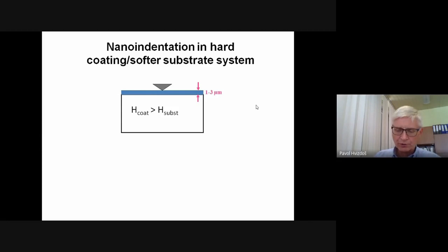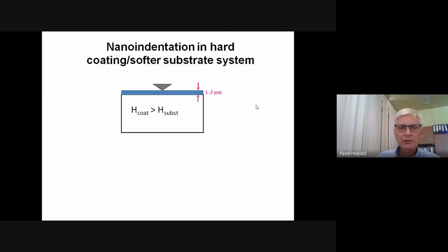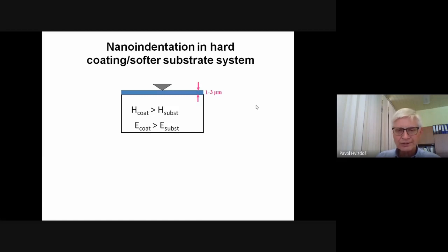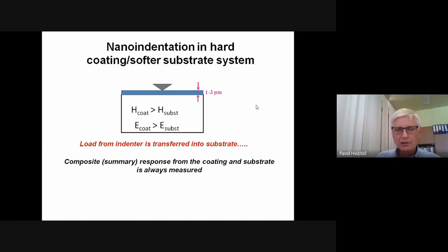This was a general introduction for mostly bulk materials. In the case of nano-indentation in coated systems, we typically use hard coatings on softer substrates to increase mechanical or tribological properties. The problem is that as soon as we have a thin coating — thin means one to three or five microns — of hard coating on a softer substrate, the load applied via the indenter is transferred to the substrate, because the stiffness, meaning Young's modulus of the coating, is also much higher than that of the substrate. Thus, we cannot measure only the response of the coating; we always measure a composite response from both coating and substrate.